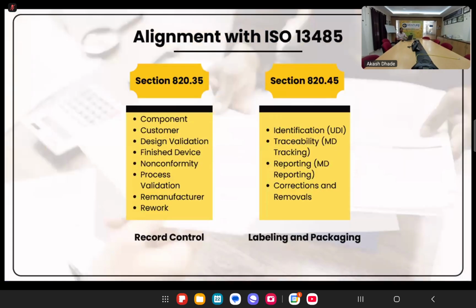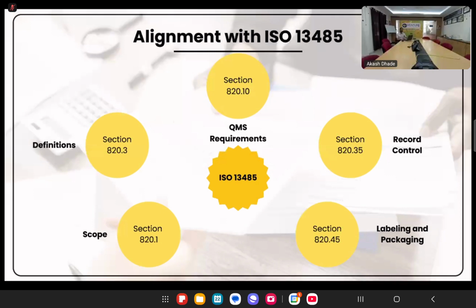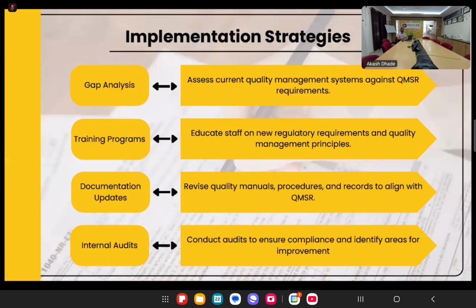So the major sections which were explained earlier, they can focus on these sections first and see if there are any changes required or any gaps in their SOPs. Okay, so you should go through the SOPs that are drafted for your QMS and see if these sections are in alignment with QMSR, and if there are any changes as per the requirement from FDA, you should make these changes. You should include some of the clauses. You should elaborate some of the SOP clauses in your quality management system. That is the first step, the gap assessment.